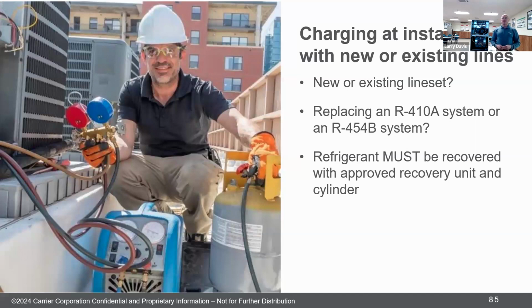New or existing line set. You're recovering refrigerant. If it's a 410A, you just go through your standard recovery process. And then when you change your units again, I just recommend flushing the line set.